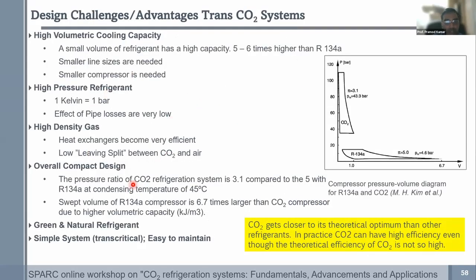I would like to spend about 5 minutes on this particular topic, over 2-3 slides. Where we have real challenges with carbon dioxide systems is that although the pressure ratios are pretty small, 3.1 with carbon dioxide as compared to about 5 with 134A, the threshold pressures are significantly high. You are operating from about 40 bar to about 110, 120 bar, so your system is much more prone to leakages.